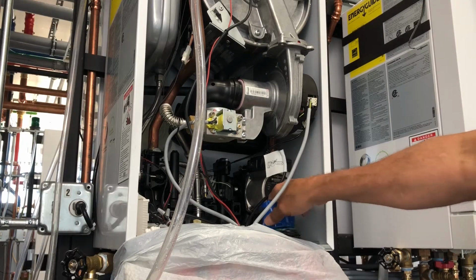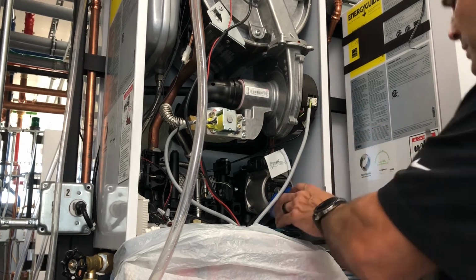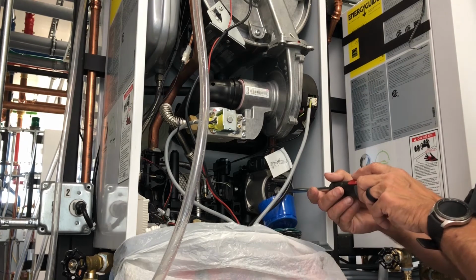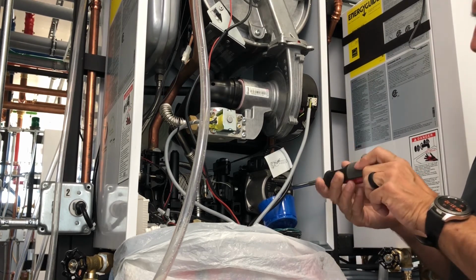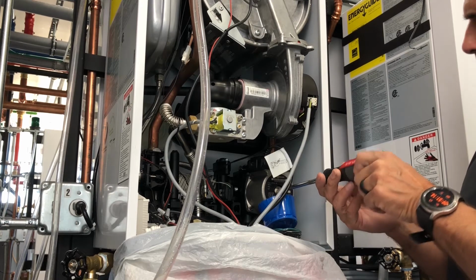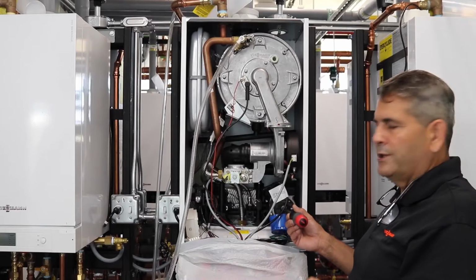You can actually stick a rag under here as well. There's not going to be a lot of water coming into this cup. Once we get it under that large nut, I'm just going to crack it to see if water comes out or if we get any type of air. We got plenty of water coming out of there, so we know we have plenty of water in there.